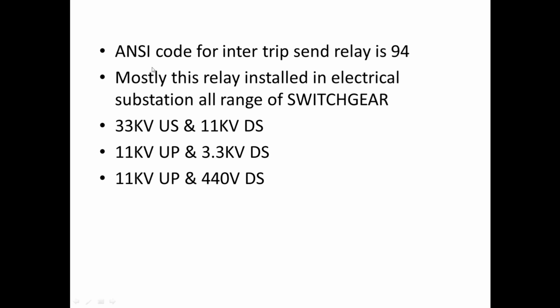As I already told, this relay is mostly used in switchgear at all ranges of voltages: upstream 33 kV with downstream 11 kV; upstream 11 kV with downstream 3.3 kV; or 11 kV upstream and 440 volt downstream. So at both ends, this 94 relay will be installed.